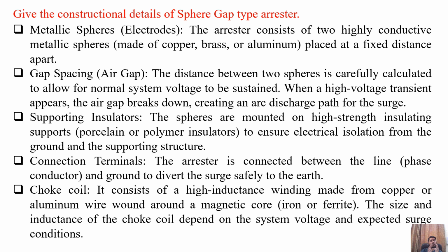When a high voltage transient appears, the air gap breaks down, creating an arc discharge path from that line to earth or ground. So it is the air gap only. So no material specific detail is required because the air itself is an insulating medium, or a conducting medium in between.